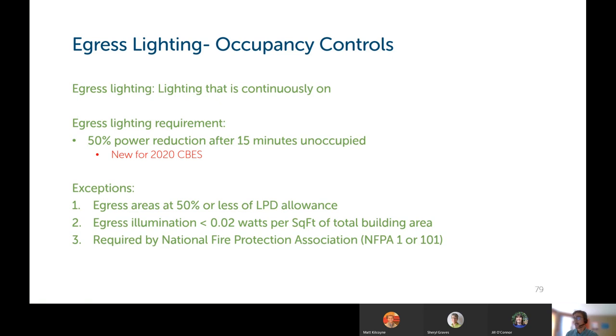Exceptions to needing to put occupancy controls on egress lighting are if the egress areas are lit up to 50% or less of the lighting power density allowances that I'll go over later. If the egress lighting is less than 0.02 watts per square foot of the total building area, then you don't need controls. Or if that lighting is required by the National Fire Protection Association's codes, NFPA 1 or NFPA 101.